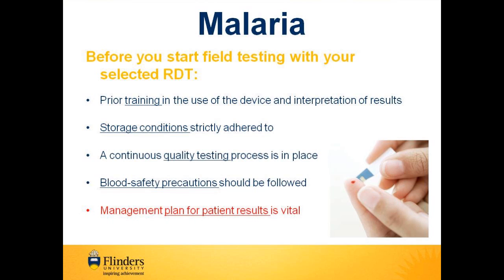When setting up field testing using the selected RDT, things that must be considered prior to the commencement of patient testing include: training should be conducted for all operators in the use and interpretation of results; storage conditions of the RDT must be continually monitored and adhered to; a formal quality testing process should be in place; blood safety precautions should be strictly followed; and most importantly, there must be a clear management plan for all patient results, as point of care testing is most effective when testing is linked to a clearly defined clinical pathway.